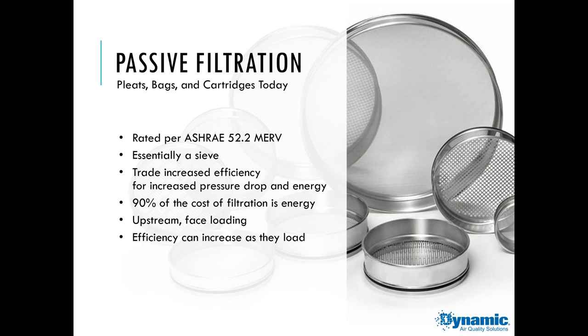So drilling down on that filtration piece, filters in North America are rated by the ASHRAE 52.2 standard, which gives them a MERV rating, which stands for minimum efficiency reporting value. And it's really aimed at comparing passive filtration devices, so filters. In brief, a passive filter is essentially a sieve, and so the trade-off, and this is an oversimplification, is pressure drop for efficiency. The more efficient it is, the harder it is to push air through it, and therefore the more energy you use. And in general, 90% of the cost of filtration is energy. It's not the cost of the device, it's the cost of the energy to push air through the device.